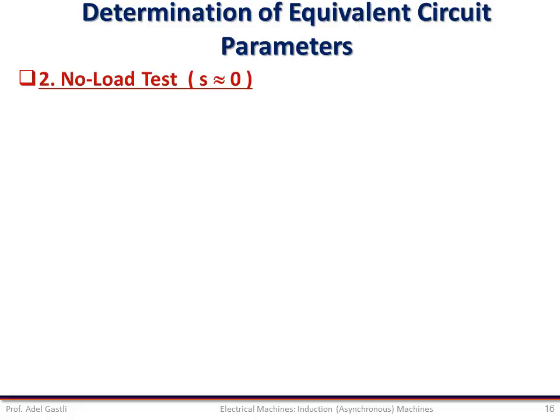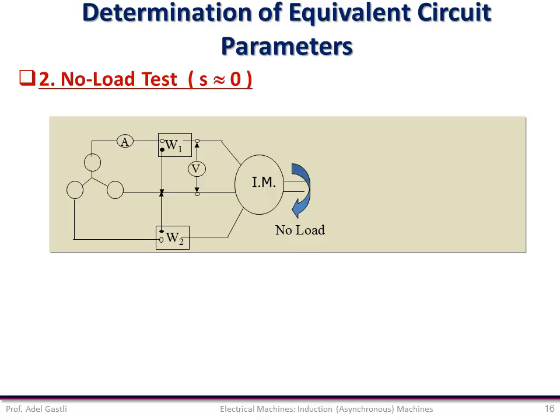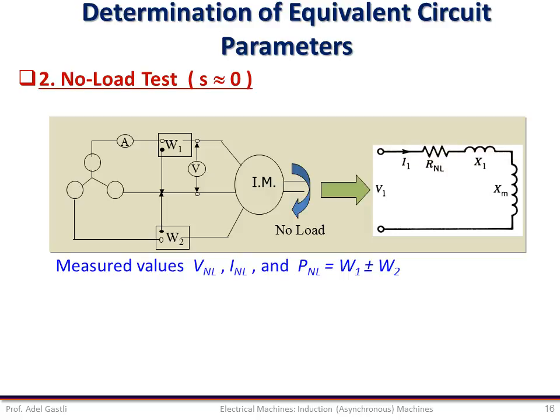The second test is the no-load test. In this test, the machine is not loaded mechanically. We apply rated voltage at the stator terminals and keep the rotor rotating freely. We measure the voltage, current, and power using one voltmeter, ammeter, and wattmeter. The equivalent circuit at no-load is equivalent to an open rotor circuit, because at no-load the slip is equal to zero, so R'2/S becomes almost infinity — an open circuit — and mainly the current flows on the stator side.